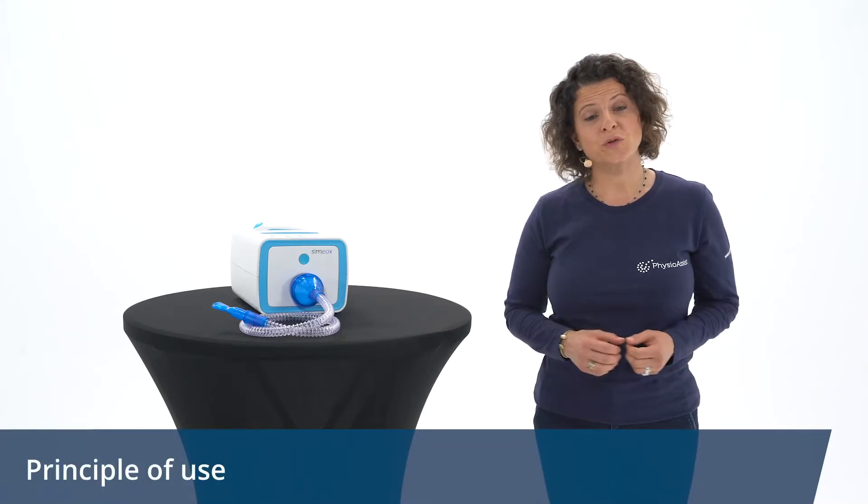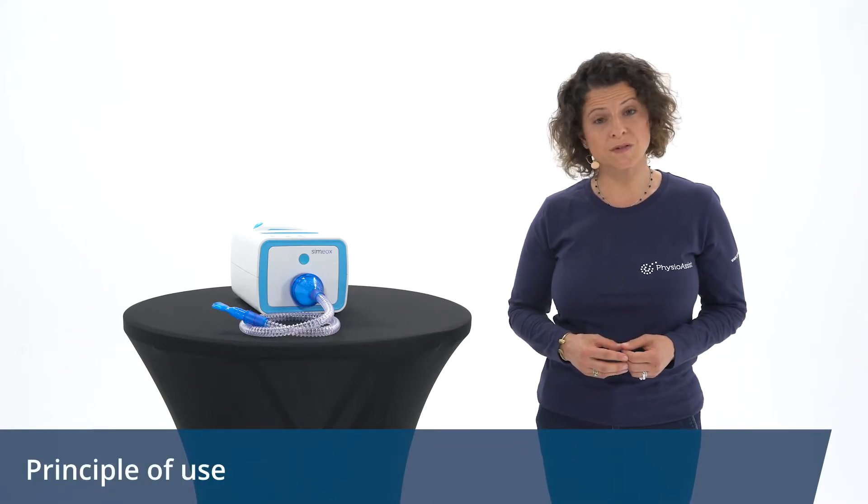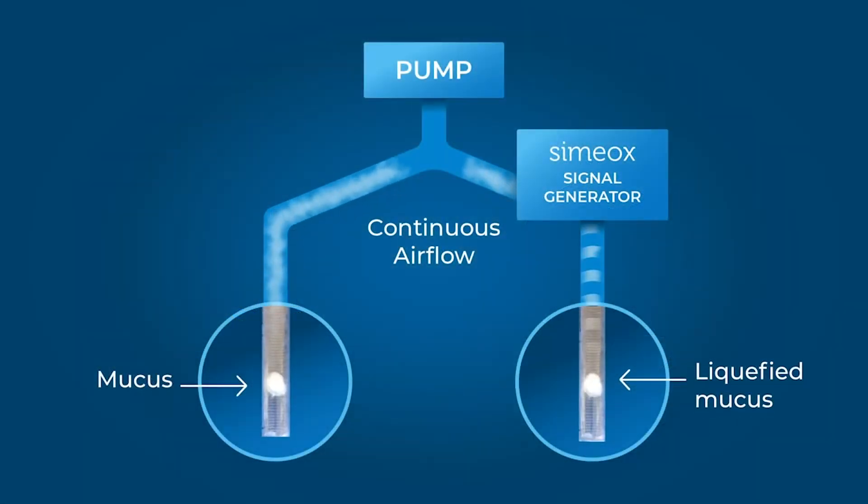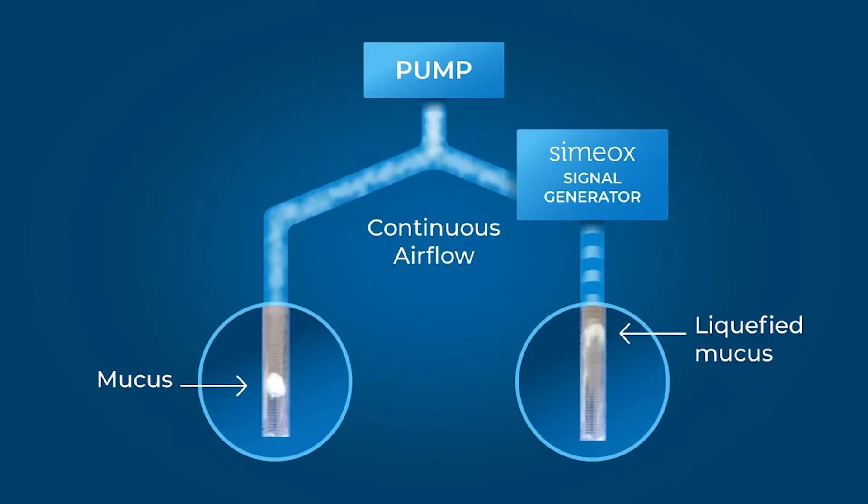This bench test assembly shows the action of the Simeox signal in a tube with mucus simulant. On the left, a pump applies a flow of 60 liters per minute. The mucus does not move.